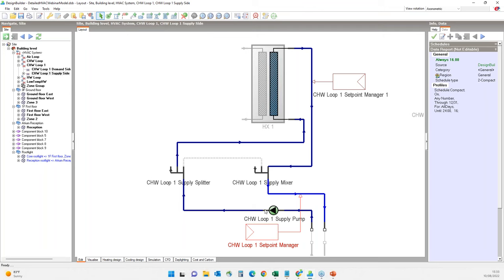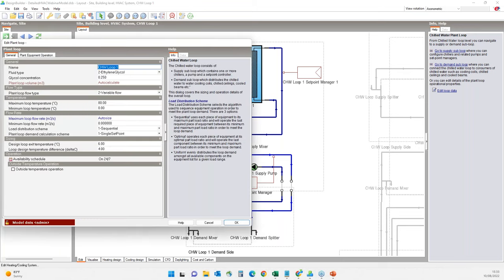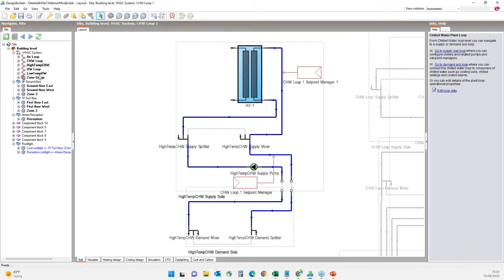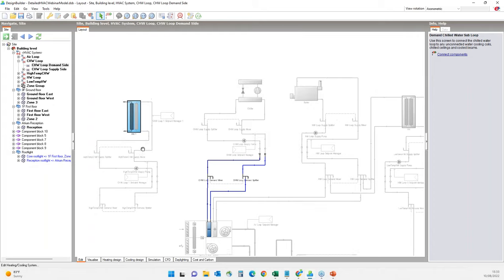Going to the loop edit dialog, I'll change its name to 'high temperature chilled water' and set the loop design exit temperature to 16 degrees with a delta of 4.